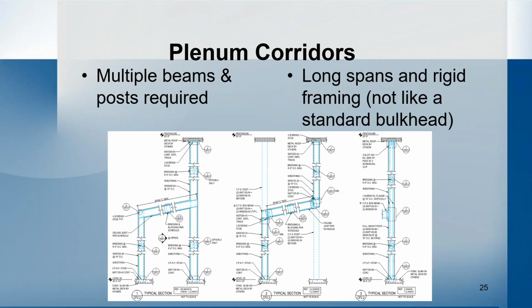So plenum corridors, so these are some typical details that we see for a typical type data center here. These typically have that higher pressure, up to 20 pounds per square foot, that we need to design for. The ceiling may be walkable at times or have a live load that's required to be placed on the framing. So they have multiple beams and posts required to frame this all out. There's long spans and some rigid framing. So this is not like a standard bulkhead that you would see in a normal type building. This is definitely a bit more complex, and this is the type of framing that definitely needs engineered, and you need to contact an engineer.